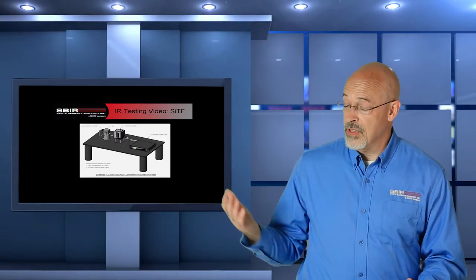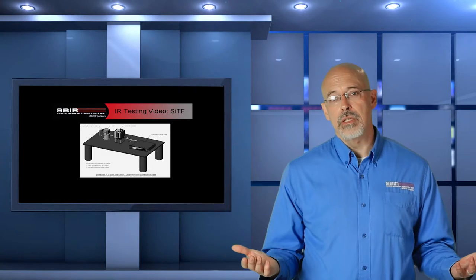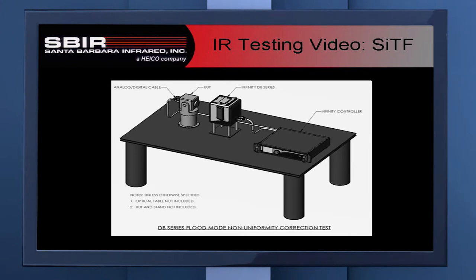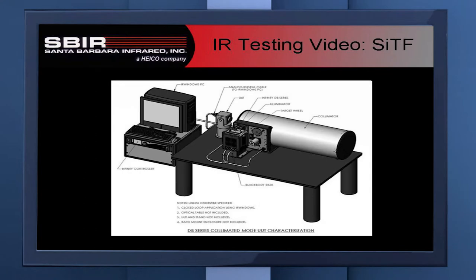The configuration shown in this slide is referred to as a flood configuration, where we take the blackbody, put it right up against the camera, and use that output temperature to stimulate the camera. We know or can measure what the output of the blackbody is and look at the response of the camera. In some laboratories there is a more involved setup — a scene projection system or target projection system — with optics used more commonly for other parts of testing but that can still be used in an SITF configuration.